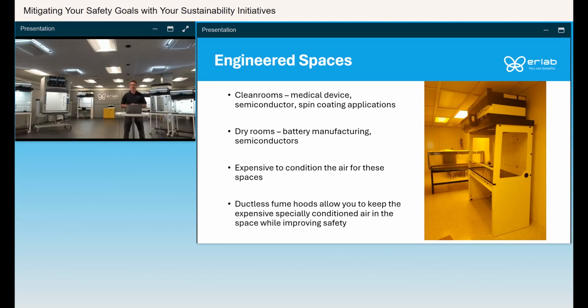Another big application for us is in battery labs. You have very dry, humidity-controlled chambers in those labs. And again, if you have a ducted fume hood in there, you're taking all that dry, conditioned air and throwing it outside. So you can have a ductless fume hood in there with HEPA and carbon filtration for the powders and liquid chemicals they're working with, and keep all that dry, conditioned air within the space.